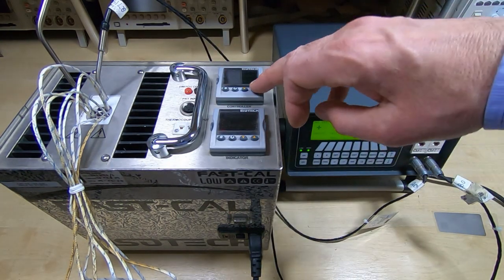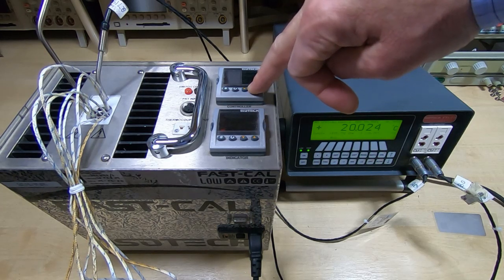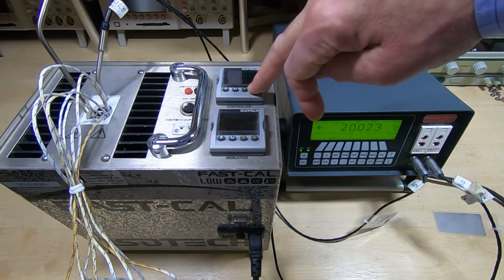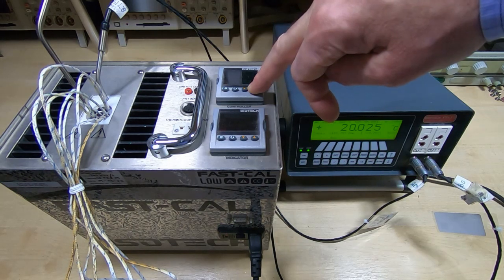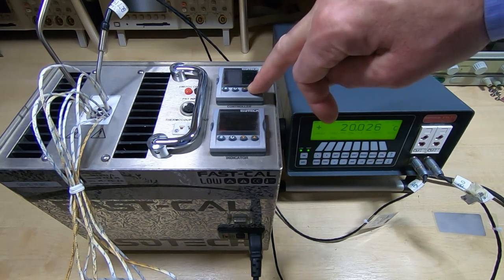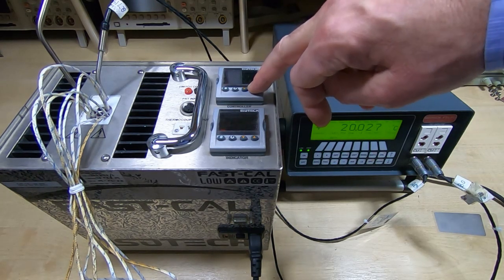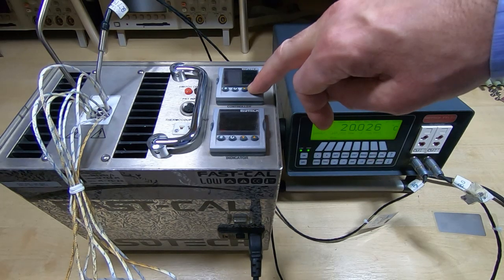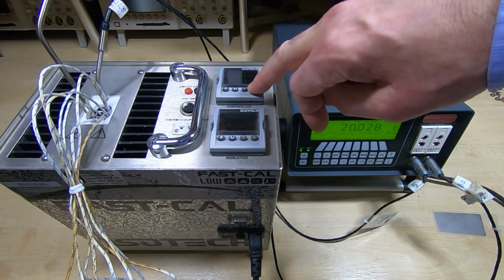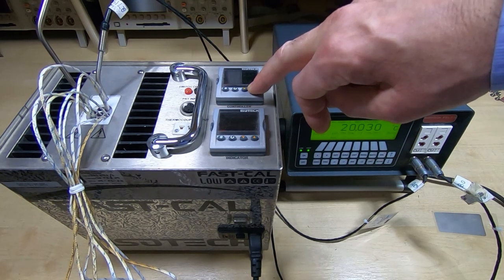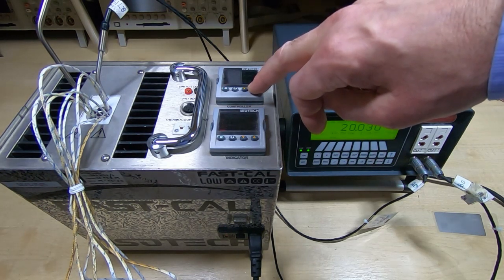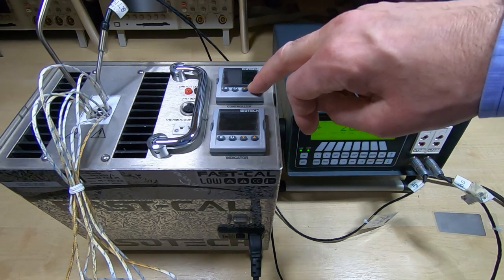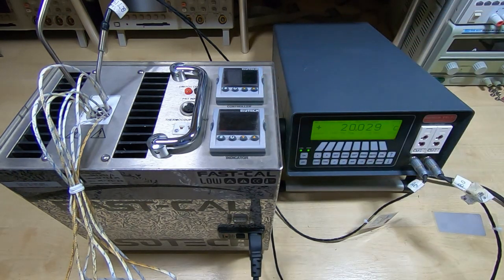So now we'll go up to the next temperature. The temperatures you select are fairly arbitrary in this case, but there are industry standards for various applications. In this case, I'm just going every 20 or 30 degrees. As I say, it's not critical, it's just to give me a good indication whether or not the probes are giving accurate results up through the range. Although we're only really interested in the higher values, in this instance I am looking to see that the heat cycle is accurate all the way up. So I've now got this set to 50. We'll come back once it's settled, look at the errors, and then go up to the next value.